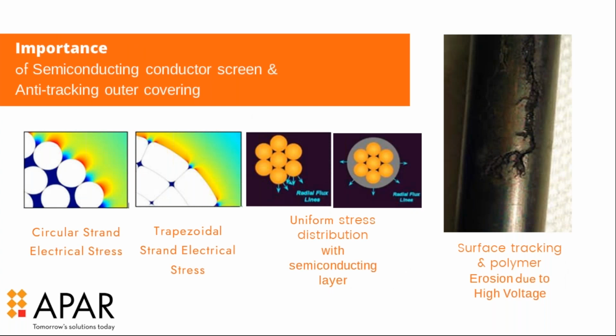Secondly, as I said, there are triple layers in the conductor. The semiconducting layer is used because the strands, whether circular or trapezoidal, create irregular electrical stresses over the surface. These stresses harm the XLPE layer if not uniform. To make the stress distribution uniform, we cover the conductor with a semiconducting layer, which uniformly distributes the stresses over the surface and prevents harm to the XLPE. That's one reason we use it.